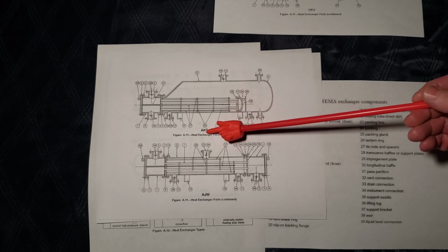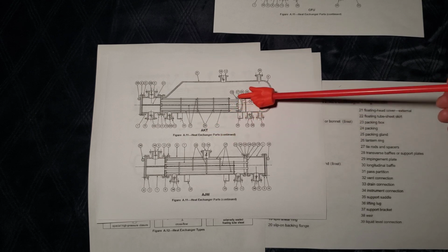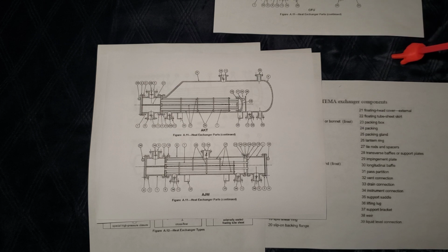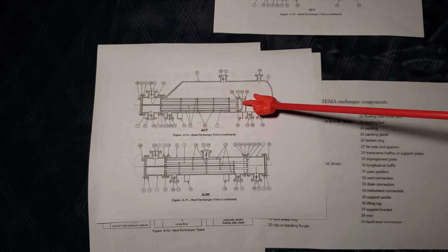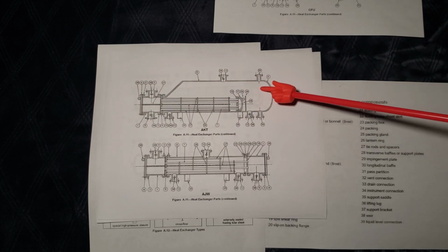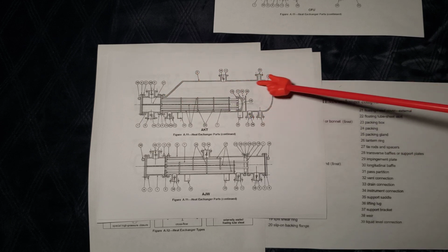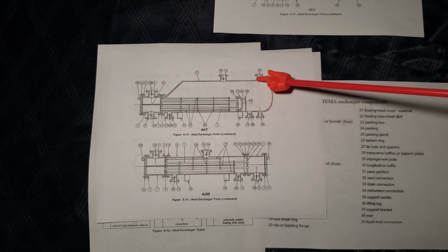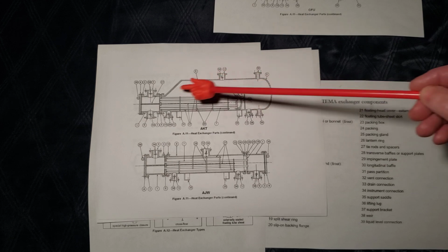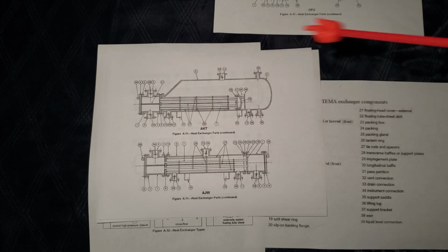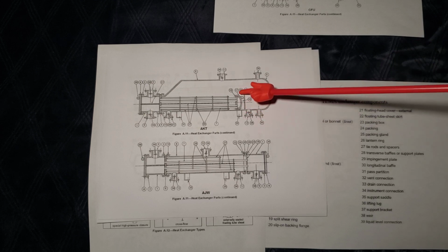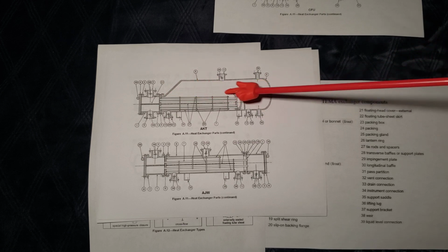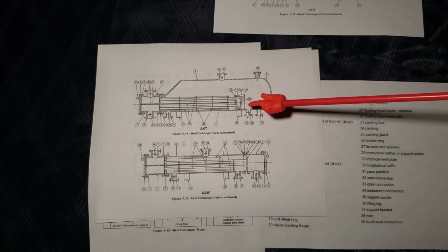So as a result, any kettle boiler will have either a U or a T style bundle. I guess you could have a couple of others as long as it was able to pass through, but it would not be an S. So for a kettle, which we can tell that it's a kettle just from the outside shape, it has a much larger maximum diameter on the body versus the mounting flange for the bundle. So we commonly refer to them as kettles, but it's still a heat exchanger. This weir wall just forces the bundle to actually have a liquid level greater than the bundle.